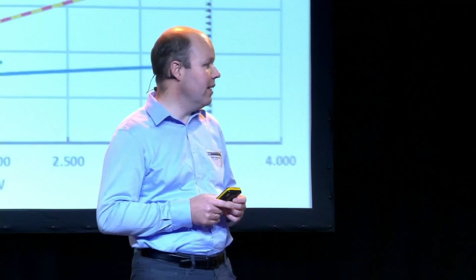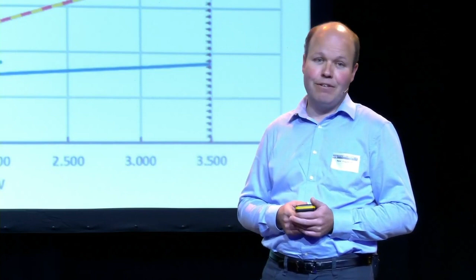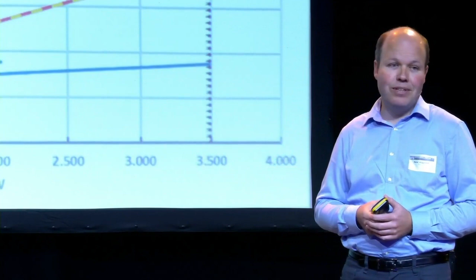Of course, this really has impact on how the process is run today, and we still need the cooling to the temperature of 60 degrees later on. But it might be an option. Before we really need the heat pump, can we use the heat directly? And of course, if you compare it to the heat pump, this has a very high COP because you need only the pumping energy to circulate the water. And 95 degrees is the highest temperature required. For the polypropylene heater, we can even use lower temperatures. For us, next best is still the heat pump.